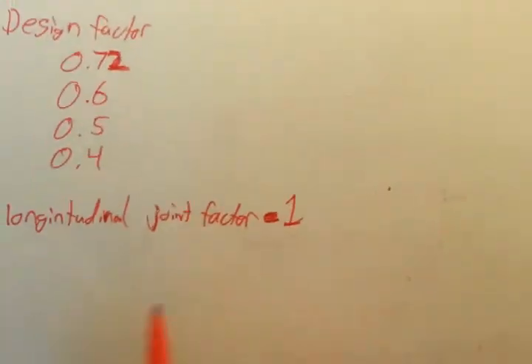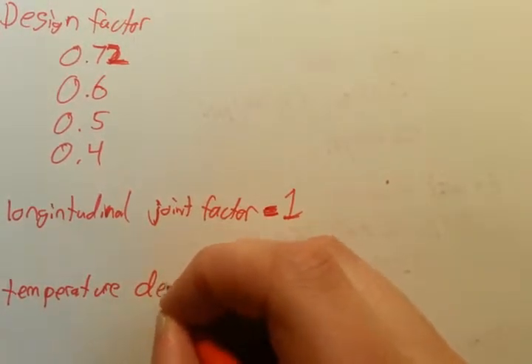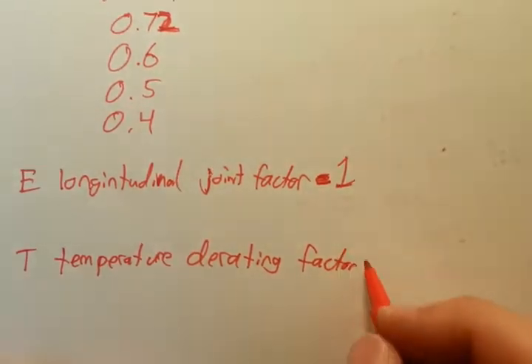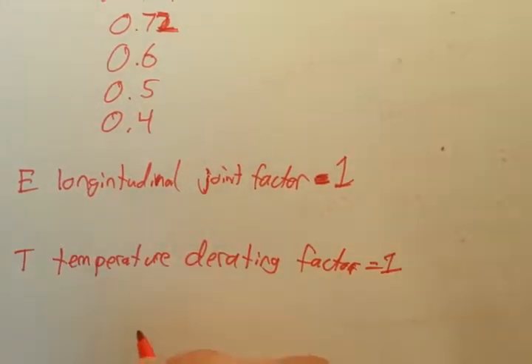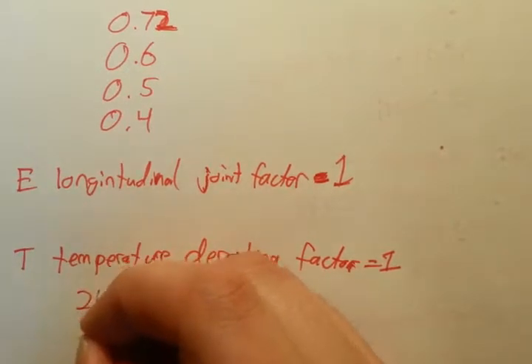The last one, T, is the temperature derating factor. This one most of the time is also going to be one. If you look in DOT 192, it gives you ranges, but as long as you're under 250 degrees Fahrenheit, it's always going to be one.